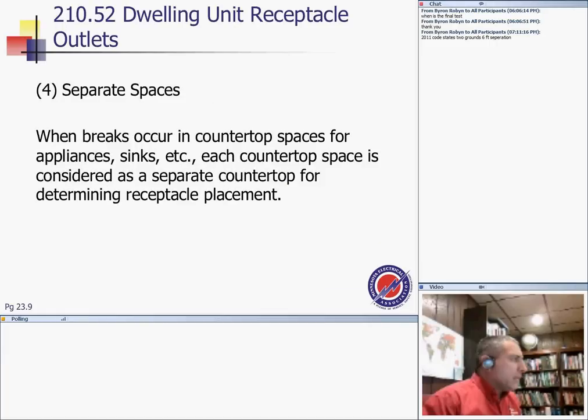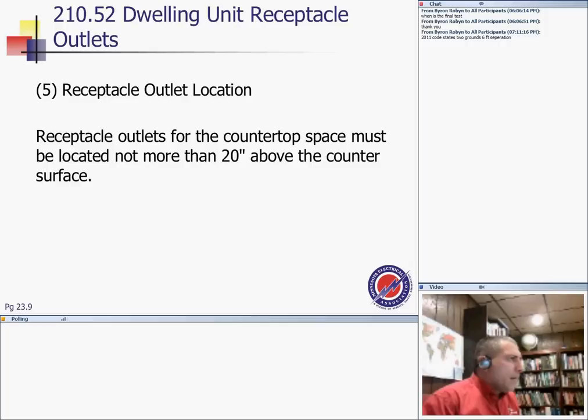Where it's broken or separated, then you start counting again. You have a sink right in here. As we all know, you grabbed your sink in here. That separation is my receptacle one here, because this is 24 inches over here. Let's just say from here to here, this happens to be 12 inches. But you need another receptacle here. And this is my sink, right there. Or you have a fridge or something, so you need a receptacle here.